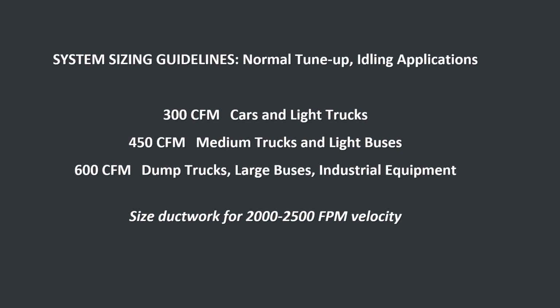So for cars and light trucks, we would use a 4-inch diameter hose and size it for 300 CFM. For medium trucks and light buses, so maybe ambulance-sized vehicles, I would use 5-inch diameter hose and 450 CFM. And then for dump trucks and semi-trucks and large buses and some industrial equipment, some agricultural equipment, we would use 6-inch diameter hose and 600 CFM. And we would size the ductwork for the 2,000 to 2,500 feet per minute conveying velocity.